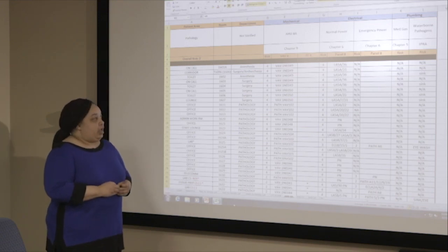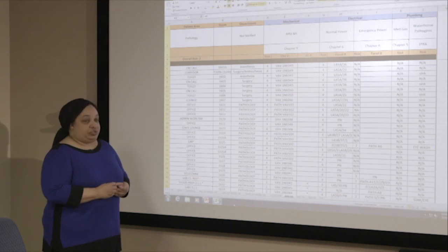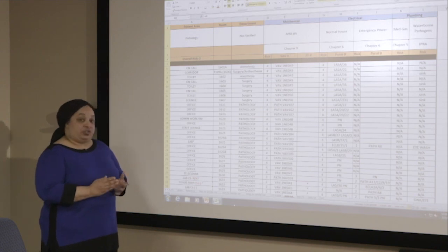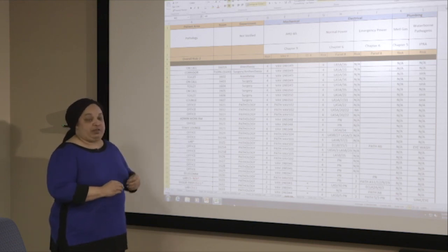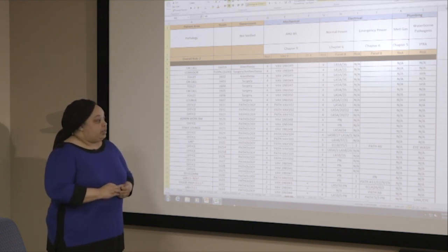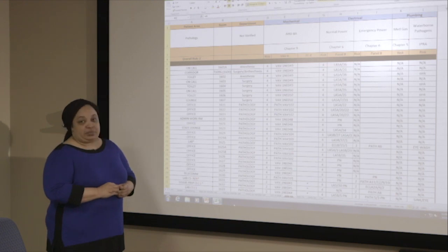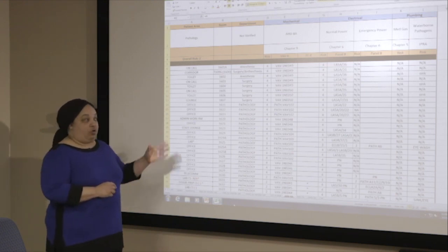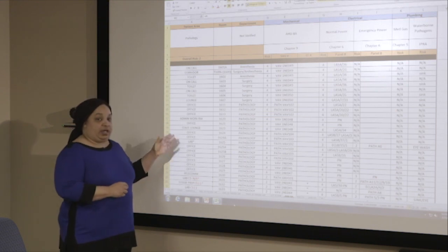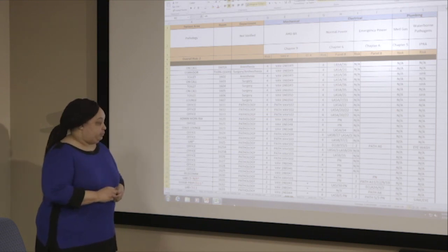sheets and we risk ranked each room. From there, we looked to see if we had any med gas and see if we had any emergency power versus normal power. And from there, we went to our spreadsheets and filled all that out. And once we did that, the next step was we risk ranked each room based on the category from NFPA and what the room usage is.